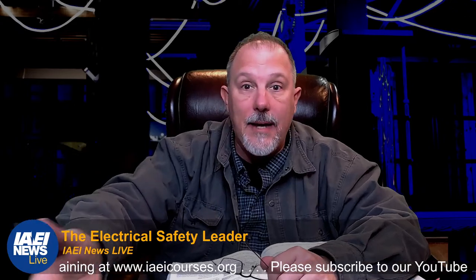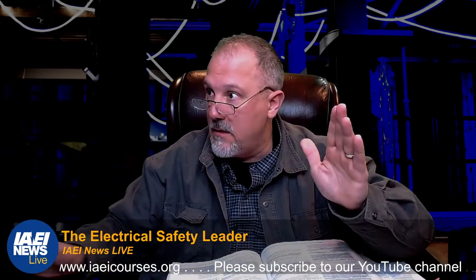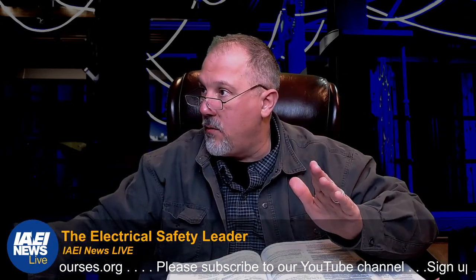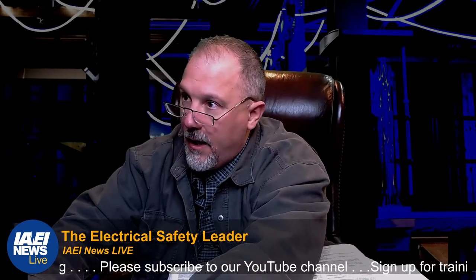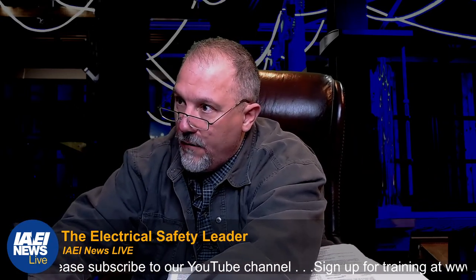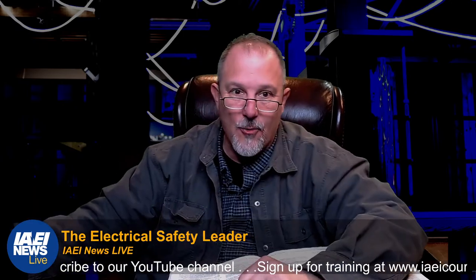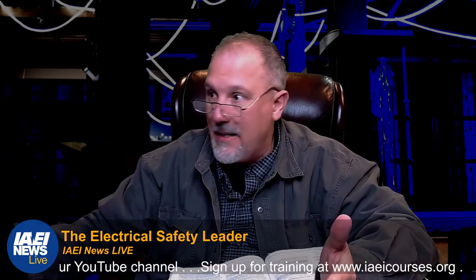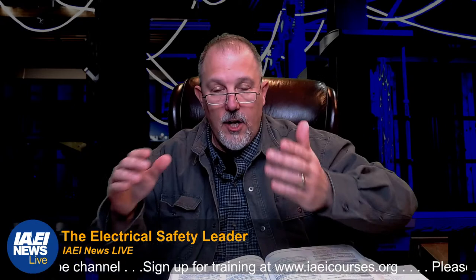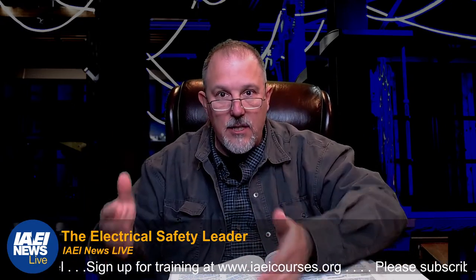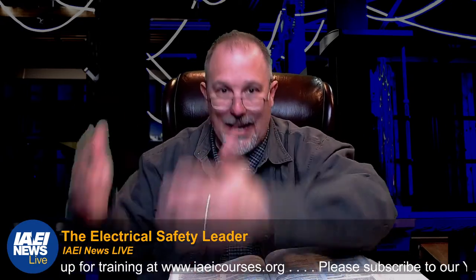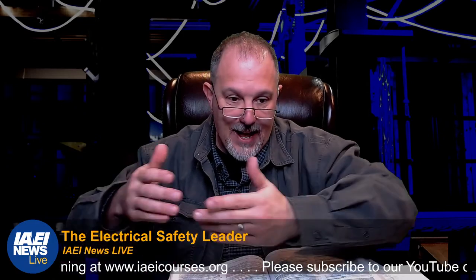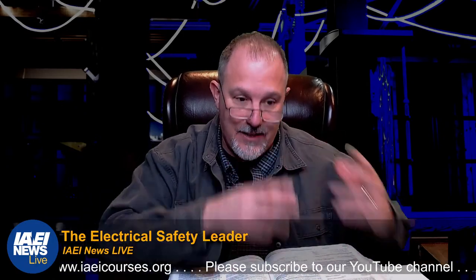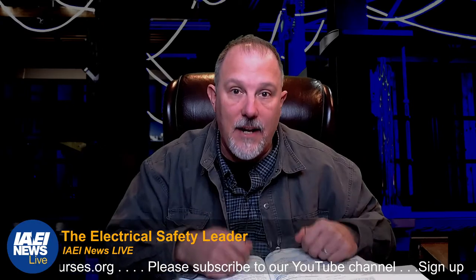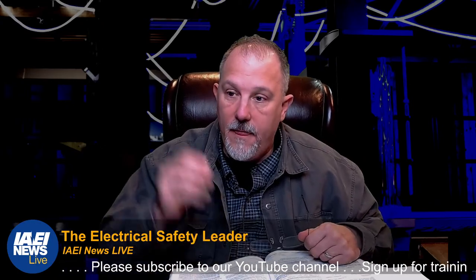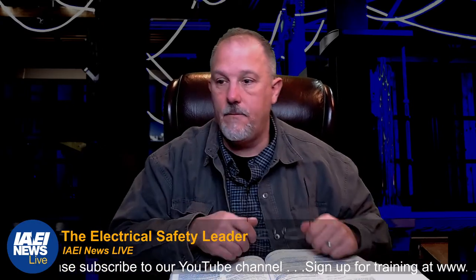It's not a UPS, because a UPS - Michael, what's the standard for UPSs? The UL standard for uninterruptible power supplies is UL 1778. So if I have a UPS, it's listed to UL 1778. If I have an energy storage system, it's listed to UL 9540. That's a big difference.